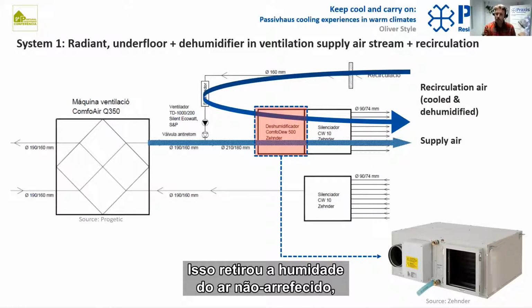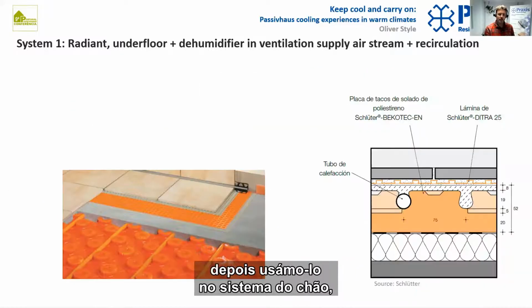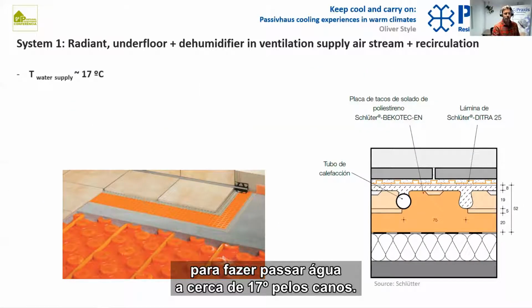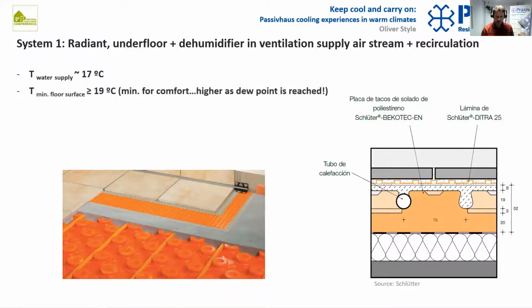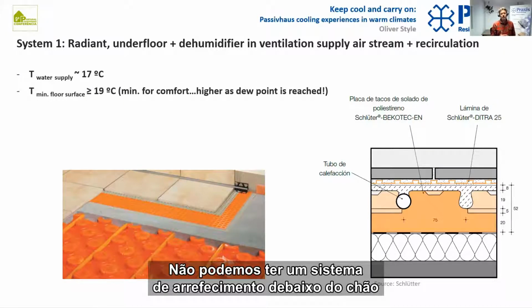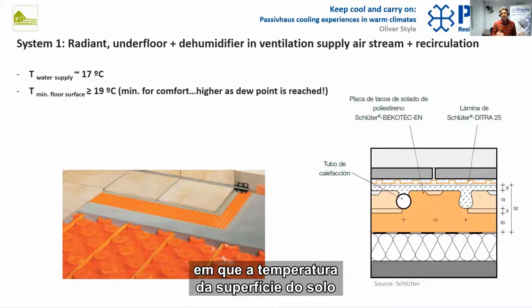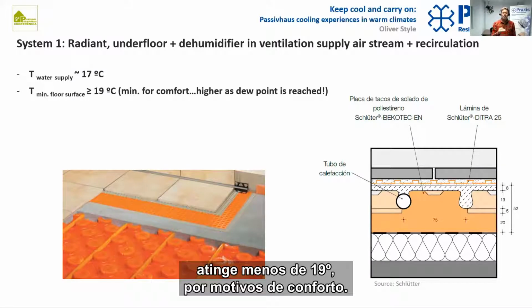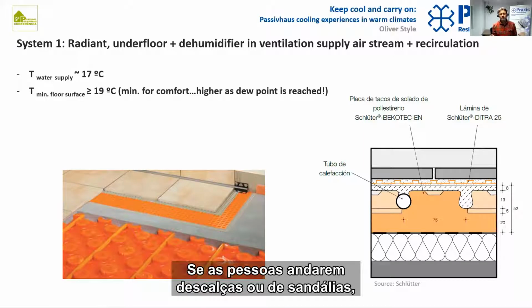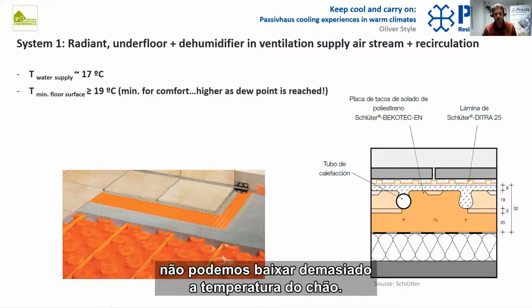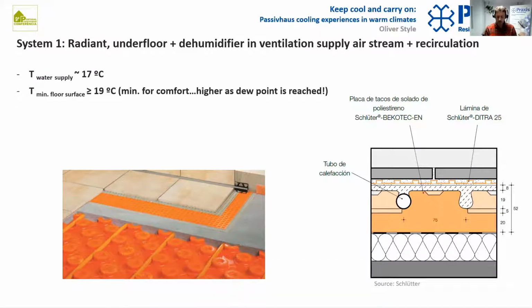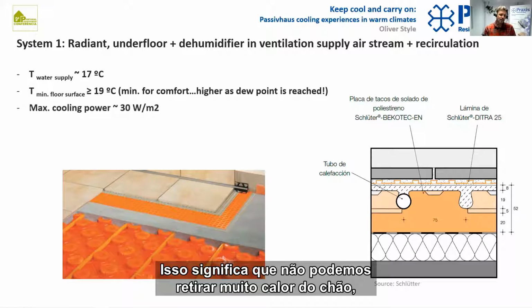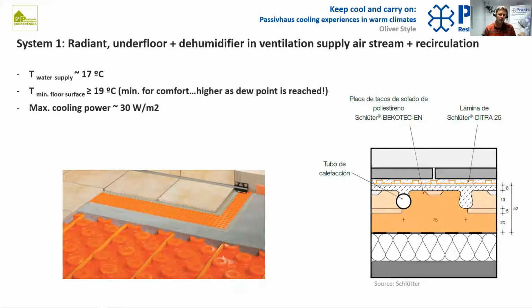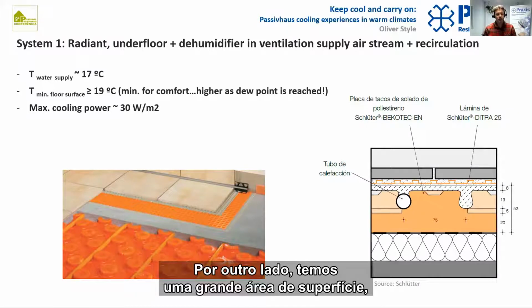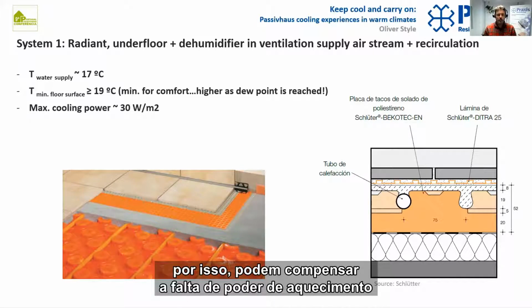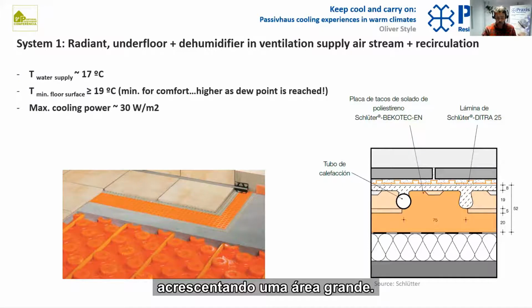Okay, so the dehumidifier was in the ventilation supply airstream with a recirculation loop here. So that took moisture out of the air and cooled the ventilation air, and then we used an underfloor system to run water at about 17 degrees through the pipes. We can't run an underfloor cooling system in which the floor surface temperature drops below 19 degrees, basically for comfort reasons. If people are barefoot or wearing sandals, you can't drop the temperature of the floor too low. So what that means is you can't get too much heat out of the floor, about 30 watts per square meter. On the other hand, you have a lot of surface area to work with, so you can compensate the lower cooling power per meter squared by having a lot of square meterage.